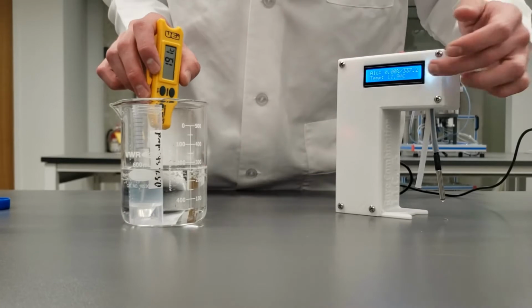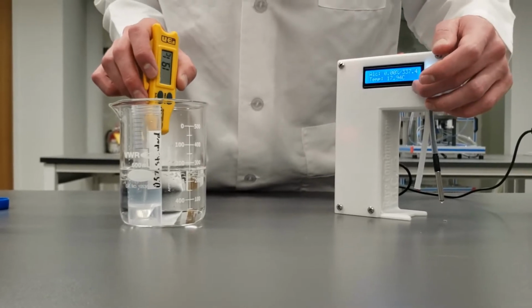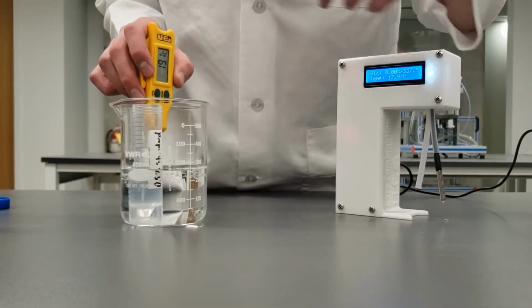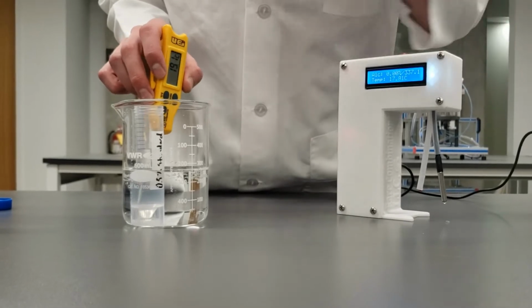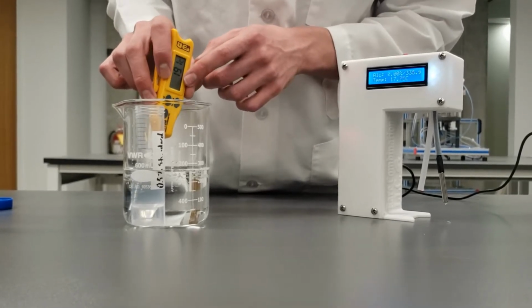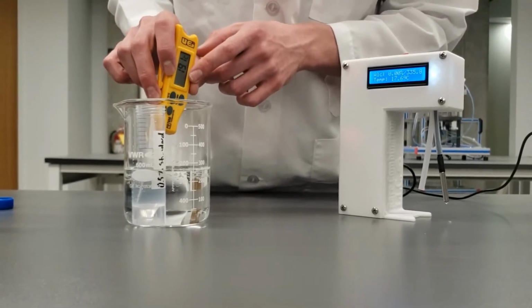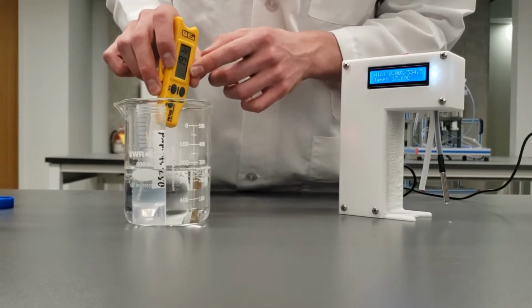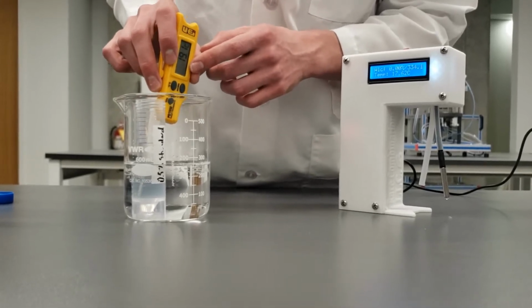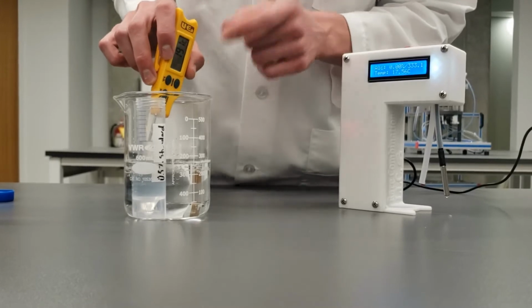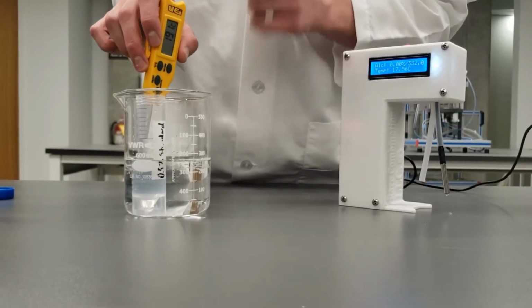So on the detector it read 20 degrees C when our sample was screwed in. So that means our water bath probably should be around 15 degrees C so that we can properly cool our standard down to the calibration temperature. So I'm going to get slightly colder water and we'll come back in a minute.